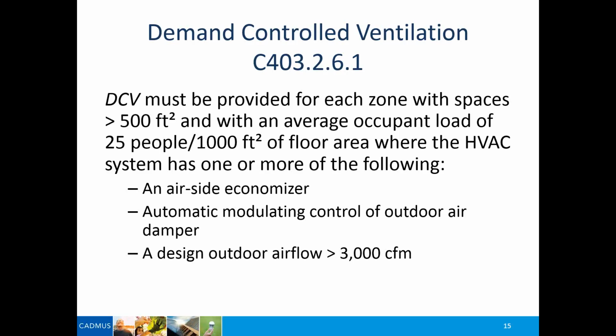And the key for demand control ventilation is to be able to modulate the ventilation air. I'm going to take a church sanctuary, for example. Let's say on Sunday the church is packed. You're providing cool air and ventilation air in that space. But during the rest of the week, no one's using the sanctuary. There's no reason to bring in that much fresh air. So you need a sensor that can determine when that system should come on and at what rate, matching the ventilation coming into the space with the number of people in the space. It's a very effective way of reducing ventilation air when it's not needed, and that could be quite a bit of the time.